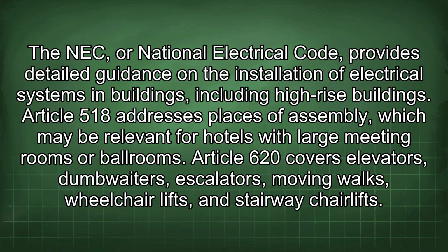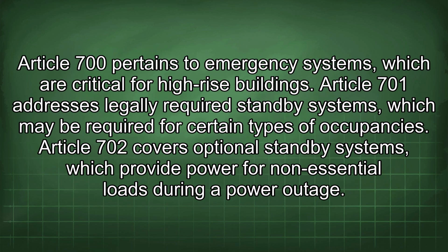The NEC, or National Electrical Code, provides detailed guidance on the installation of electrical systems in buildings, including high-rise buildings. Article 518 addresses places of assembly, which may be relevant for hotels with large meeting rooms or ballrooms. Article 620 covers elevators, dumbwaiters, escalators, moving walks, wheelchair lifts, and stairway chair lifts. Article 700 pertains to emergency systems, which are critical for high-rise buildings. Article 701 addresses legally required standby systems, which may be required for certain types of occupancies. Article 702 covers optional standby systems, which provide power for non-essential loads during a power outage.